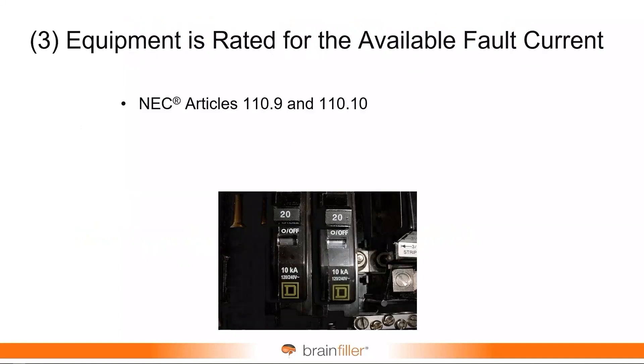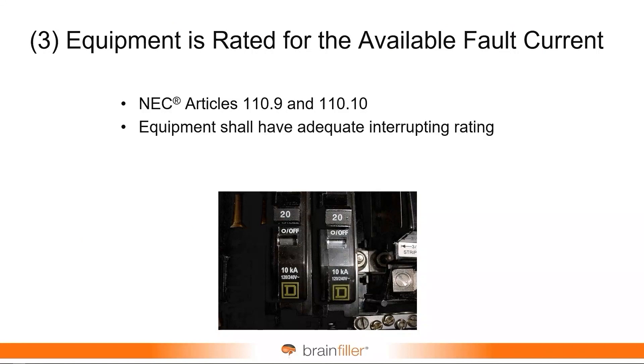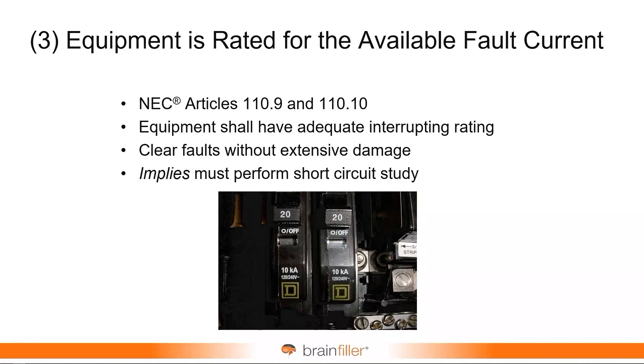For example, if you have equipment that has a certain interrupting rating, the National Electrical Code requires that the equipment has to have an adequate interrupting rating. And now you see that in NFPA 70E. It doesn't specifically state that you have to perform a short circuit study, but it kind of implies that you do to verify that the equipment has an adequate interrupting rating.